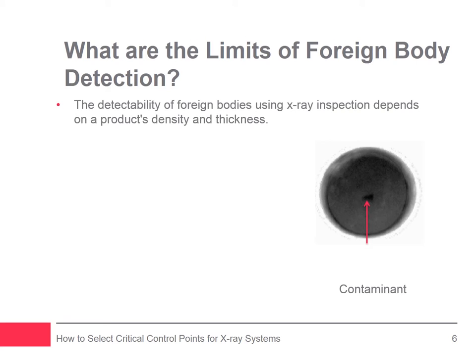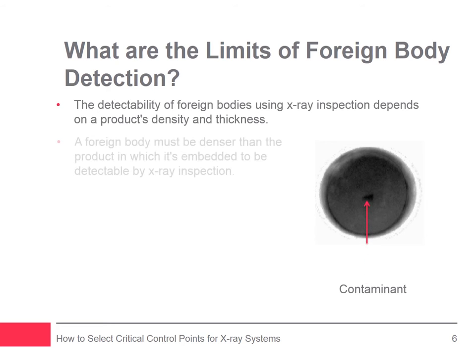The detectability of foreign bodies using x-ray inspection depends on product density and thickness. Product density determines the depth of gray in the grayscale x-ray image — the denser the product, the darker the gray. To be detectable by x-ray inspection, a foreign body has to be denser than the product in which it's embedded, meaning it will absorb more x-rays and show up as an area darker than its surroundings. Any foreign body with a density similar to or less than that of the product is incapable of being detected. As product thickness in the path of the x-ray beam increases, so does its overall level of absorption, making detection more difficult.